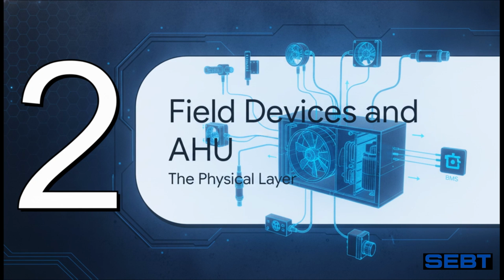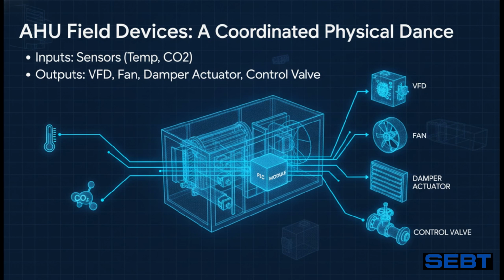Moving right along to Section 2, field devices and the AHU, basically the physical layer of the air handling unit. Now, inside a modern AHU, the environment is just packed with specialized devices. On the input side, we are constantly pulling in live data from temperature, humidity, pressure, and CO2 sensors. All this raw physical data gets wired directly into the analog and digital input modules of our controller. Now, on the flip side, the PLC uses that exact data to command variable frequency drives, or VFDs, which precisely control the exact speeds of our supply and return fans. It's also commanding damper actuators to mix outdoor and return air, and it's modulating control valves to let the precise amount of chilled or hot water into those coils. It is quite literally a highly coordinated physical dance.